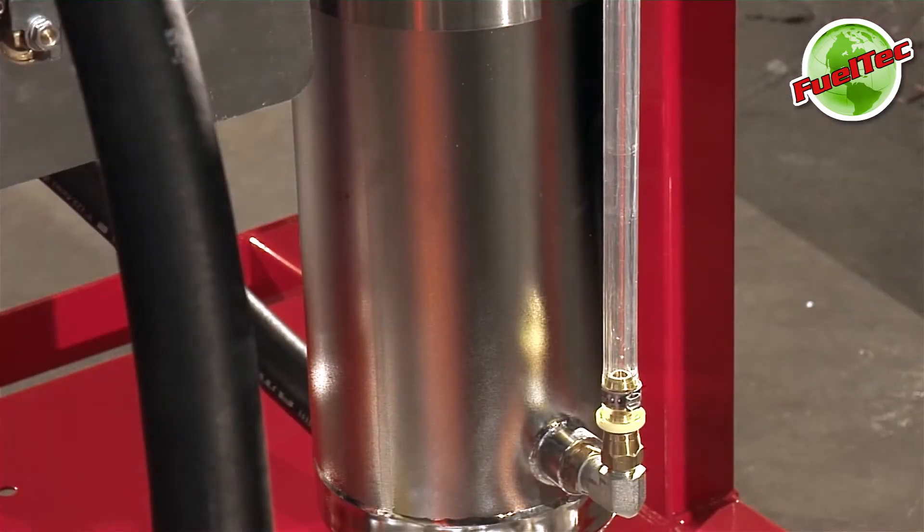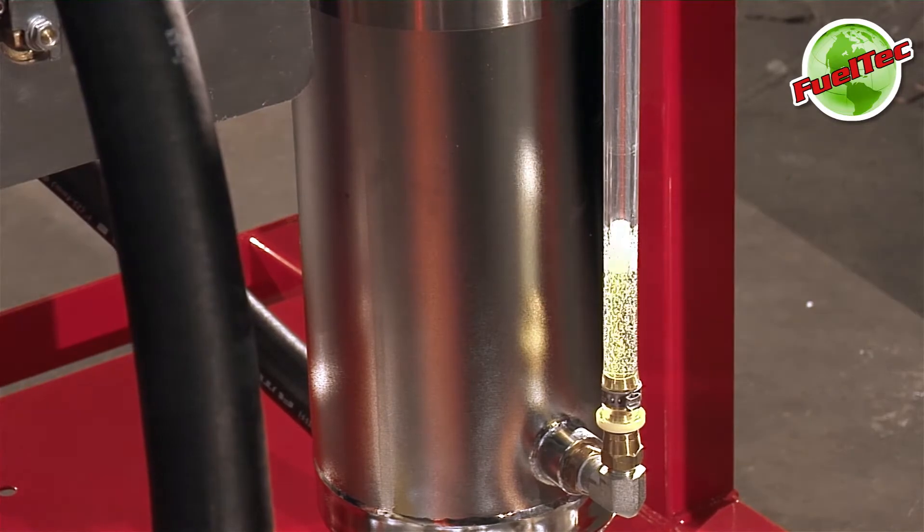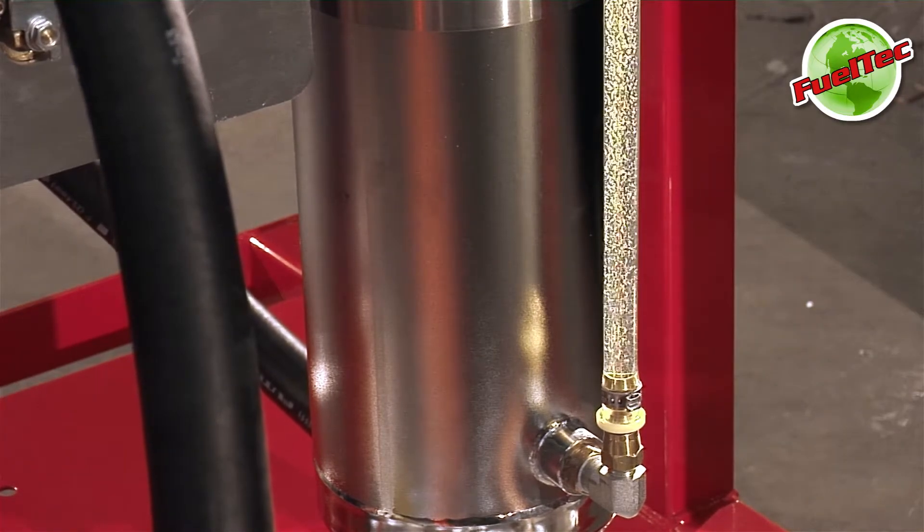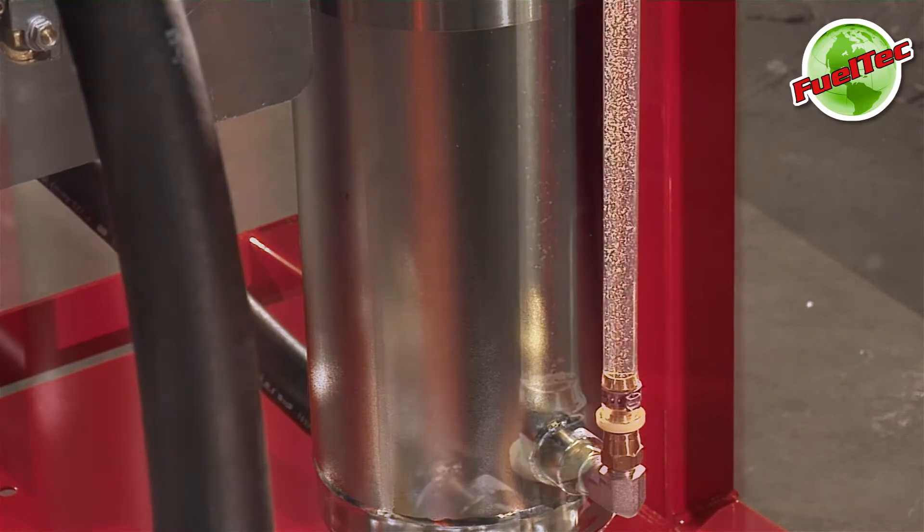Observe the sight tube as the fuel level rises. Make sure to notice the fuel color. When the sight tube is full of fuel, lower the pickup tube to the tank bottom to begin removing water.